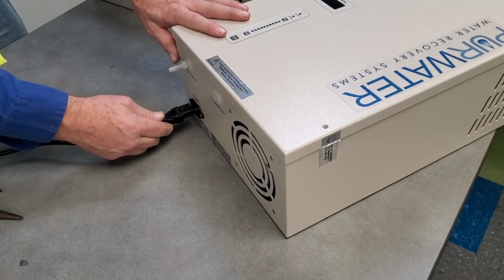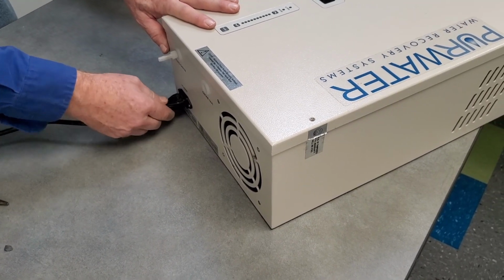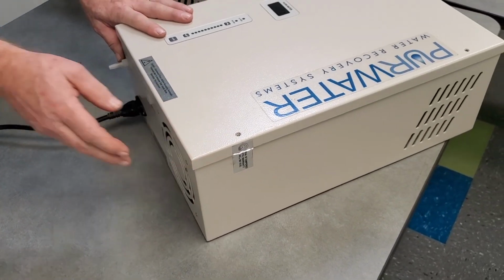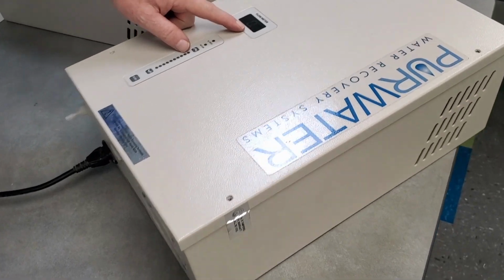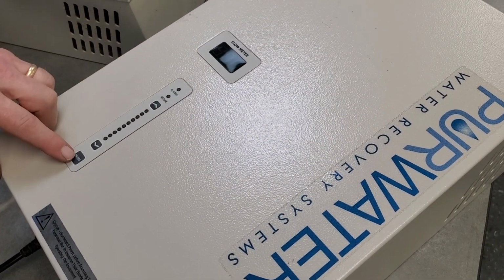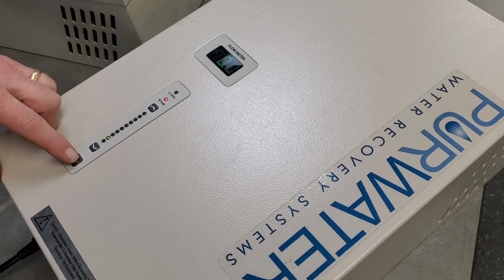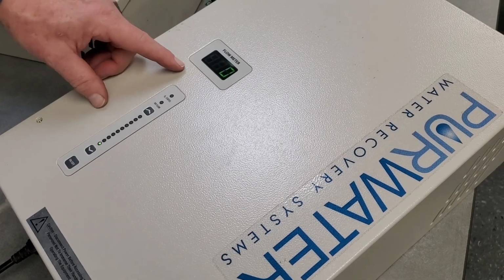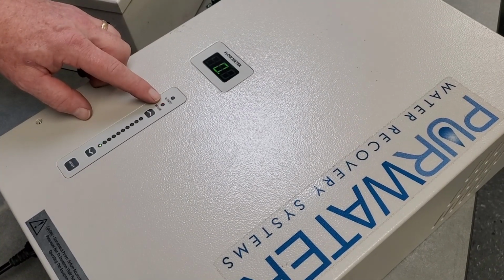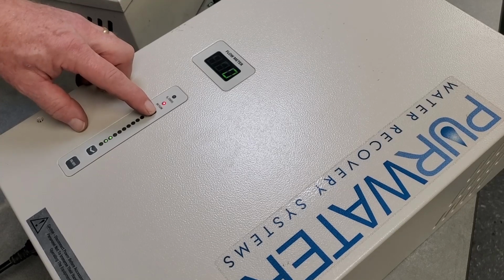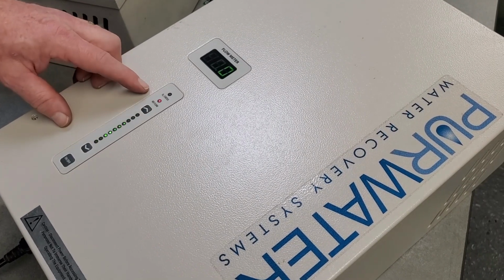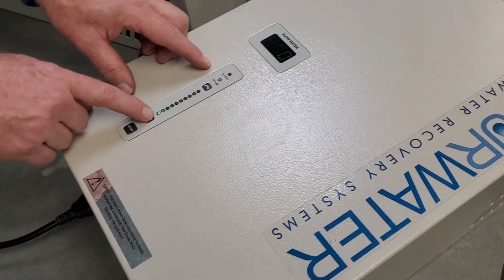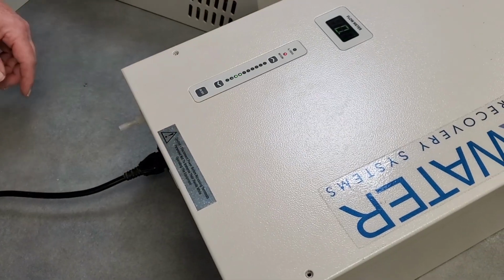Okay, so I'm going to put some power to this unit, and you notice as soon as I put power to it that this will light up with kind of a dim reading. If I press the on switch, it gets brighter, and it also is telling you that there's no flow. And I can set the amount of power that the ozone generator will make. Right now it's not turning on because there's no flow.